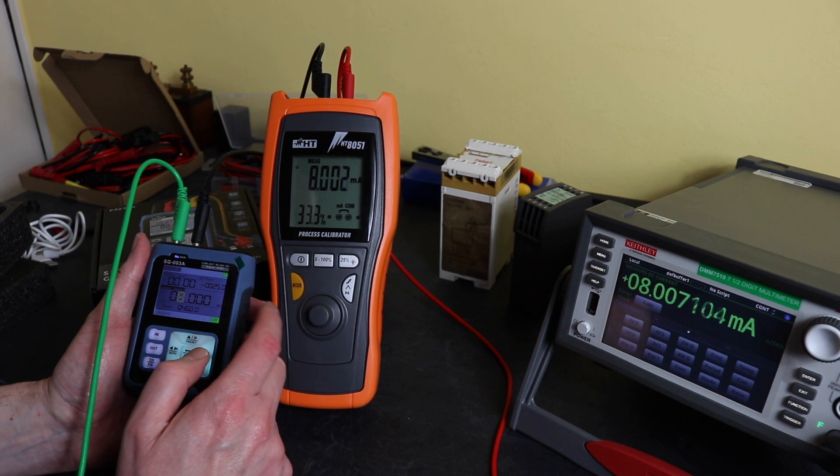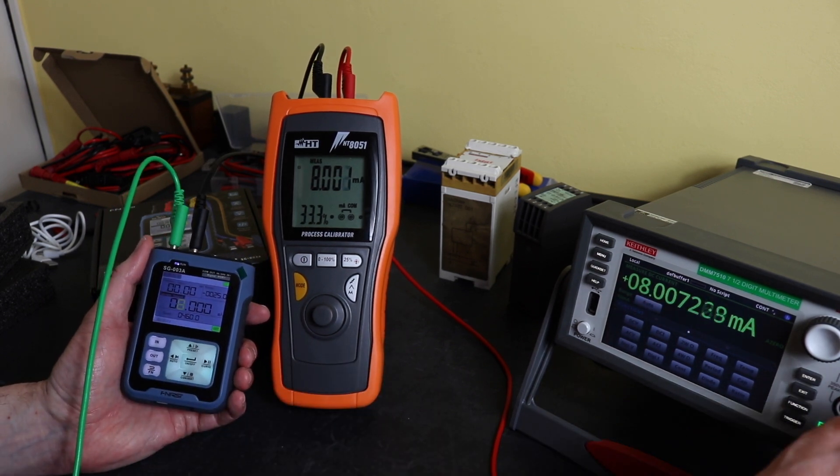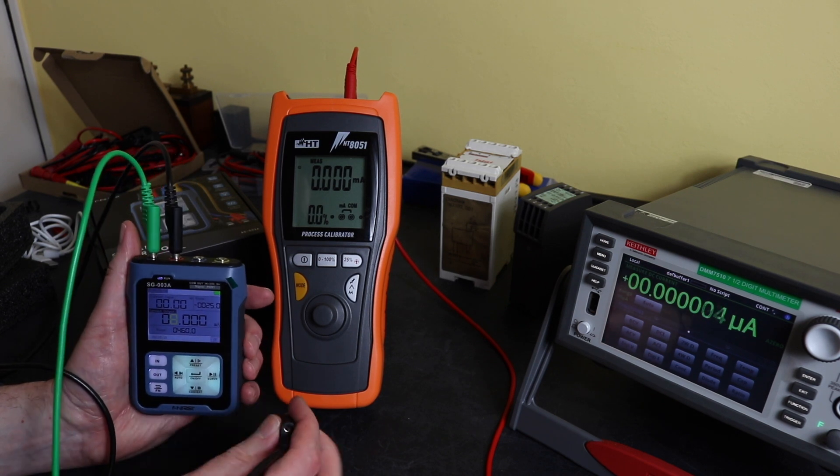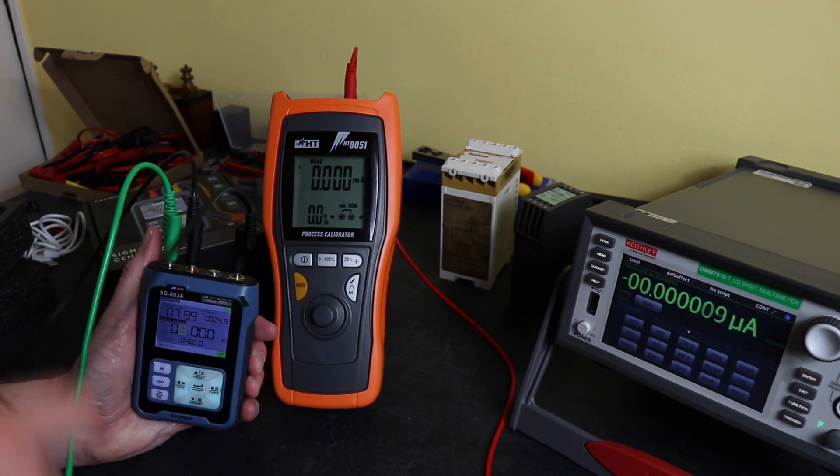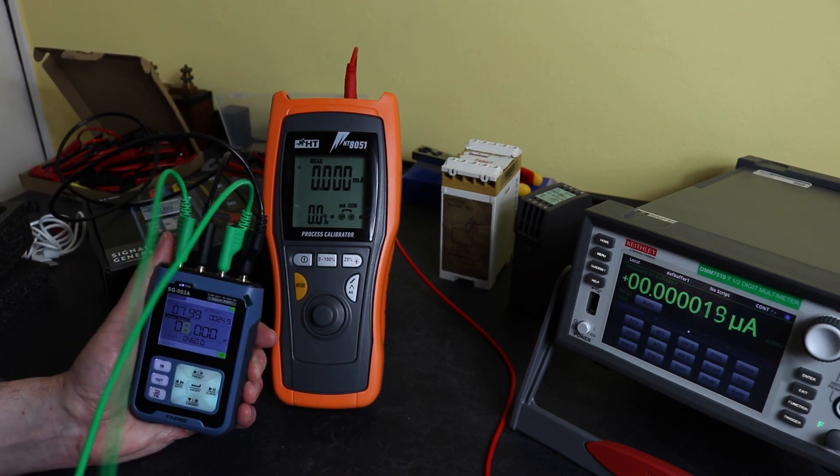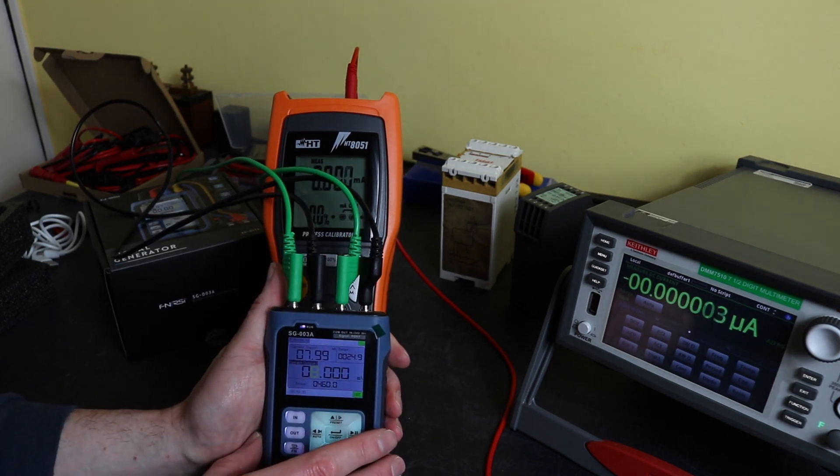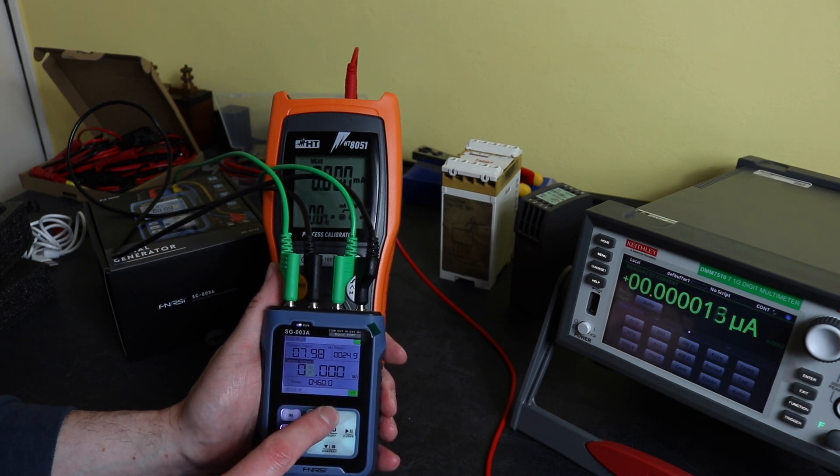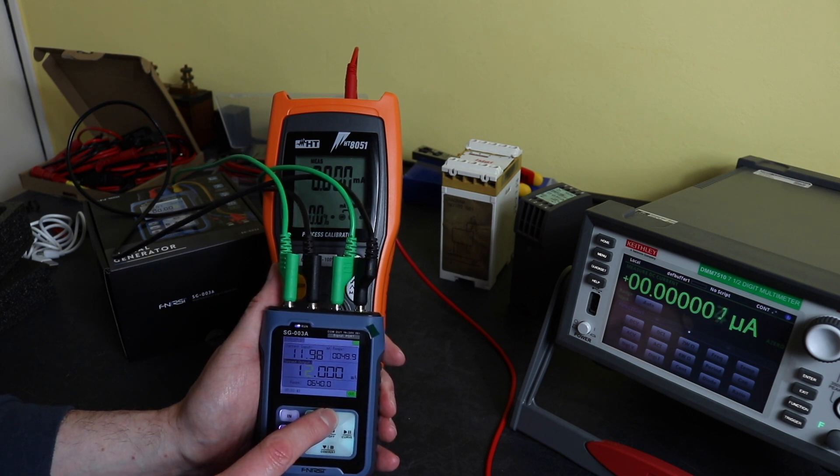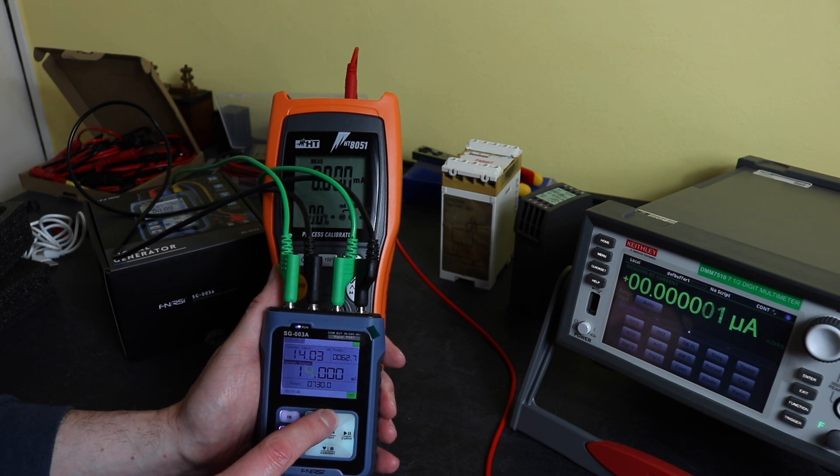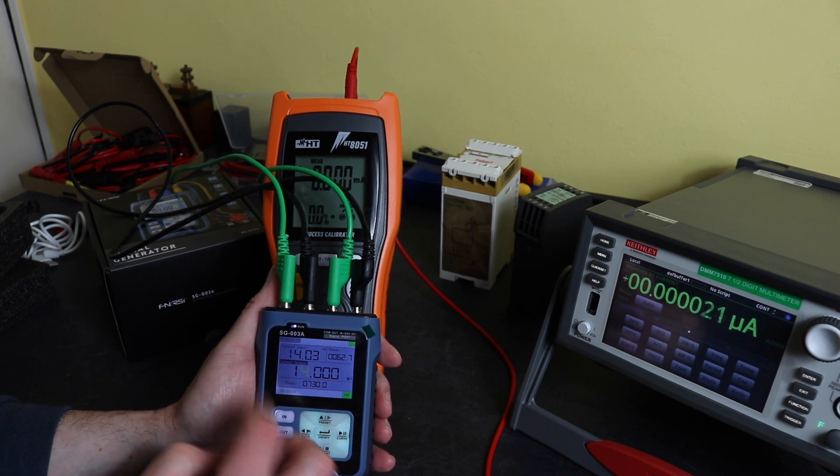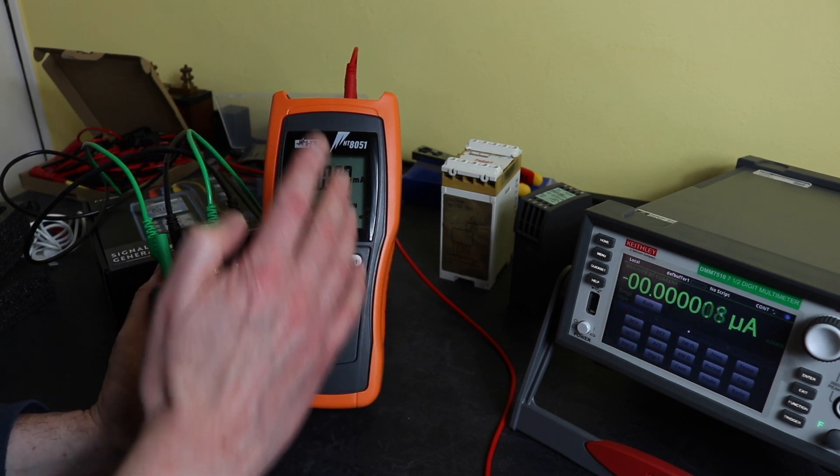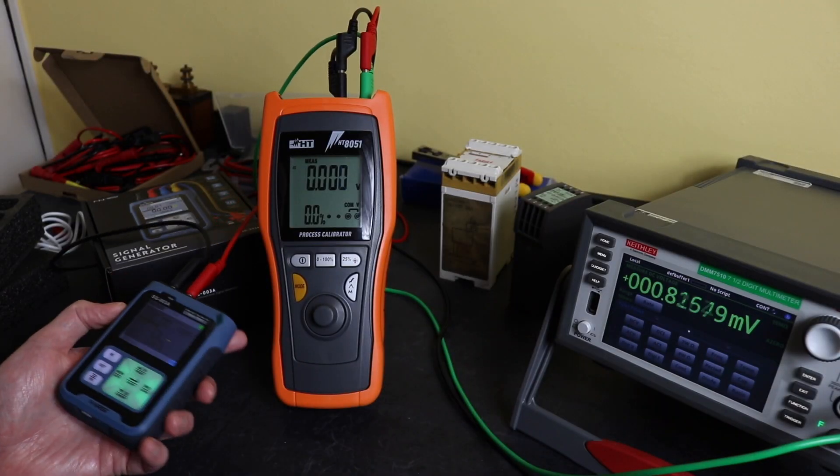What this unit can do that this unit can't is it can actually supply and read at the same time, because the meter is permanently in circuit. I can merely go right around and I've got eight milliamps going out, reading 7.99 on this as well. And then if I choose to change, there's 12, 11.98, 14. So yeah, you can check the instrument out itself, which you can't do with the HT8051.